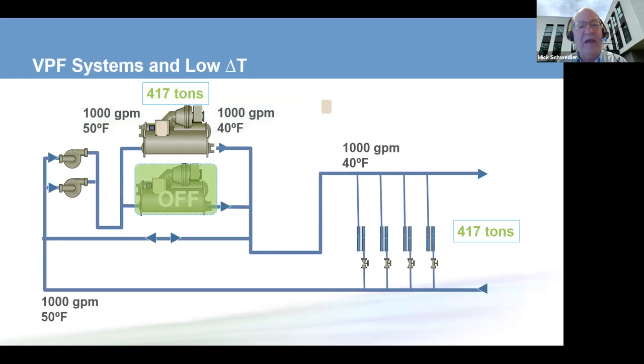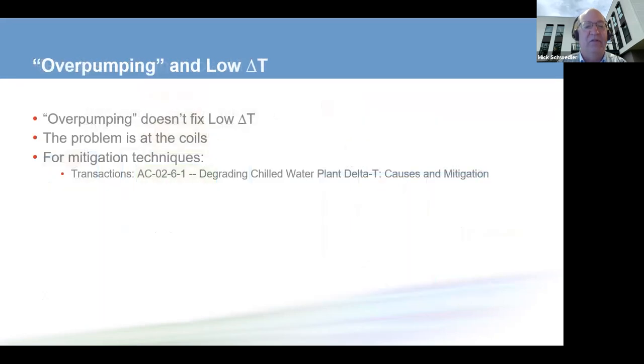So this is what happens in our system. We now pump, instead of 750 GPM through the chiller, 1,000. We satisfy the flow rate, we satisfy the loads, and we are working well, with the exception that we're pumping a lot more water than we should be, and our system efficiency might not be as good.